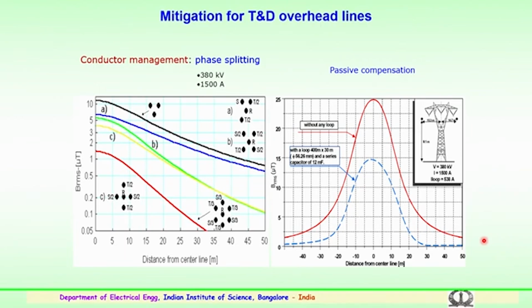So, further on conductor management, there is one more option, like phase splitting. A typical example is shown here for a 380 kV transmission line carrying a current of 1500 amps, and you can see for various configurations A, B and C how the performance of the magnetic fields from the center is shown. You can see how the configuration is given here, so that this will improve the performance and give better information to the utility engineers who could plan how properly the conductor management could be made for reducing the magnetic fields or the electric fields particularly.